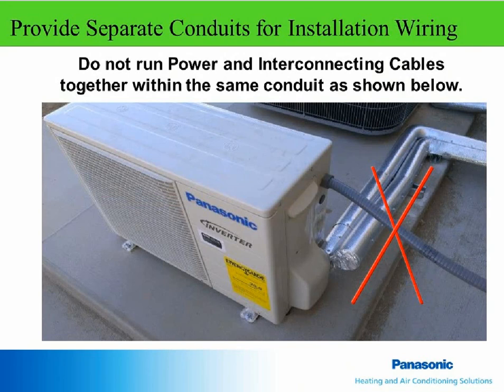This picture shows only one conduit connected to the outdoor unit. This means that the power supply to the outdoor unit and the interconnecting wires to the indoor unit share the same conduit. These should always be run separately, or it could lead to communication problems and error codes. This system might run perfectly for days or weeks between issues, and it could lead to an ongoing problem job.